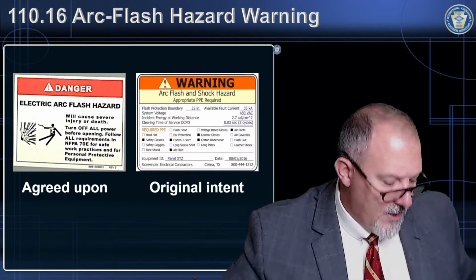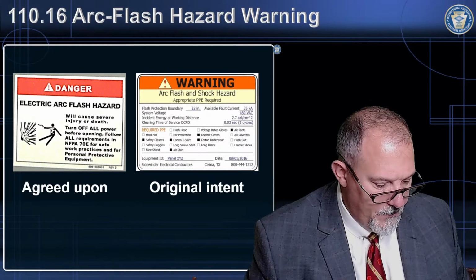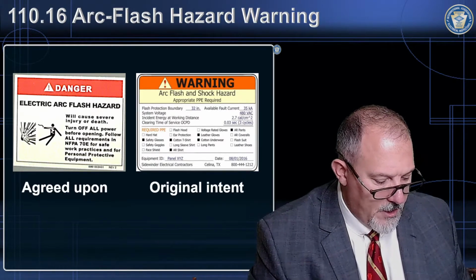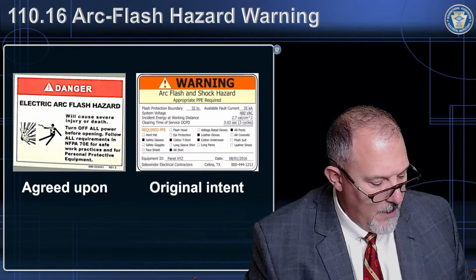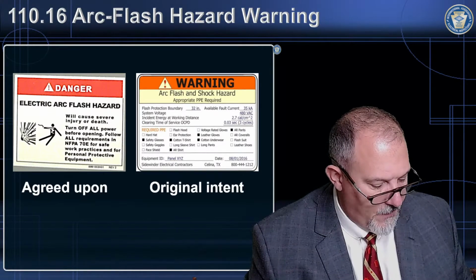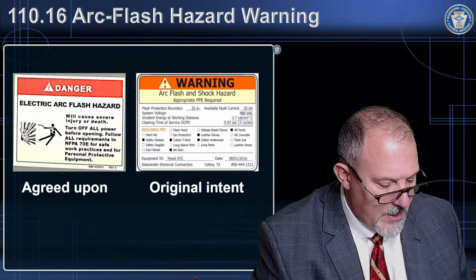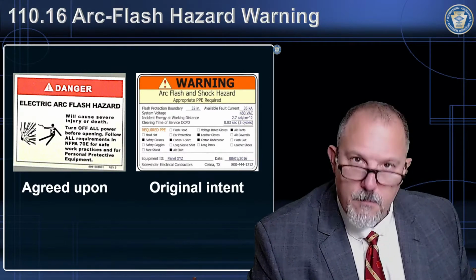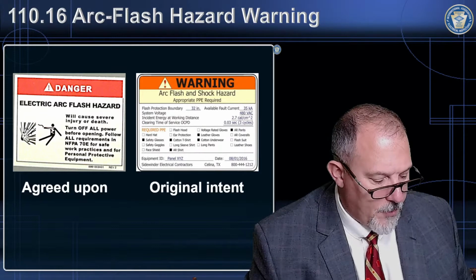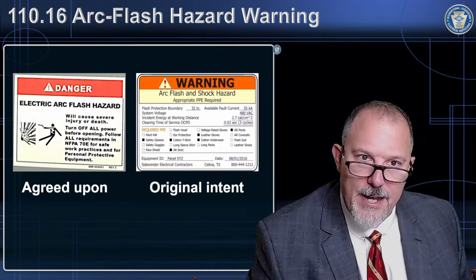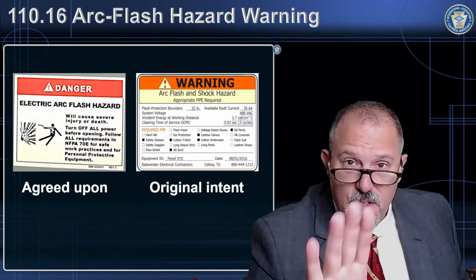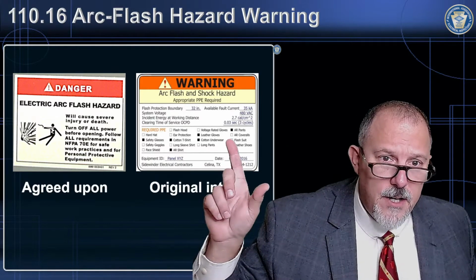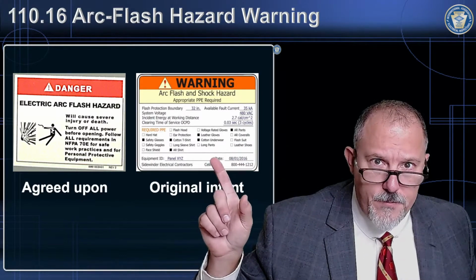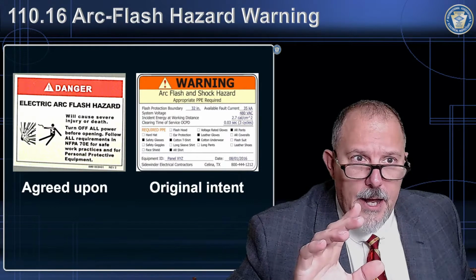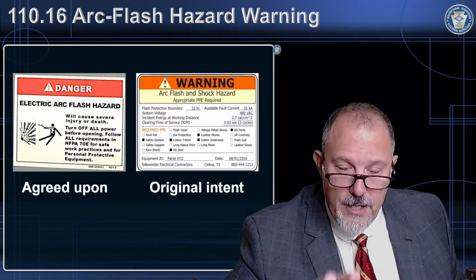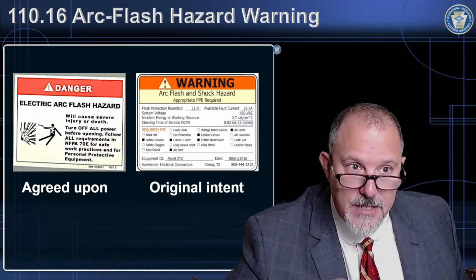Now, in this language, it also says the marking shall be located so as to be clearly visible to qualified persons before examination, adjustment, servicing, or maintenance of the equipment. But it also says shall be field marked to warn the qualified person of the potential electric arc flash hazard. Now, if you think about it, it's field marked. That's a very generic label over there. And the initial language read that it has to be field marked.